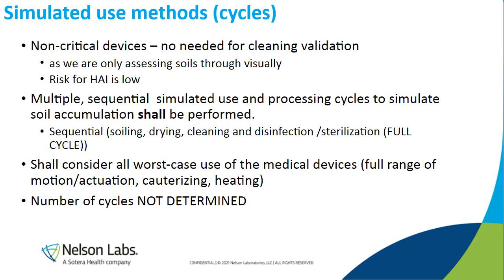What you want to understand with these cycles is that you are processing them through how they would be processed in a clinical setting. So you're just putting it through patient use, which is soiling, and all the cleaning processing that will happen on that product. So if it's cleaning and disinfection, then that's what you're assessing. If it's cleaning and sterilization, that's what you're putting through the simulated use cycles. Now, this is a must for critical and semi-critical devices. So anything that will be punctured through the body into the bloodstream, or anything that is going into mucous membranes, simulated use cycles is a must.